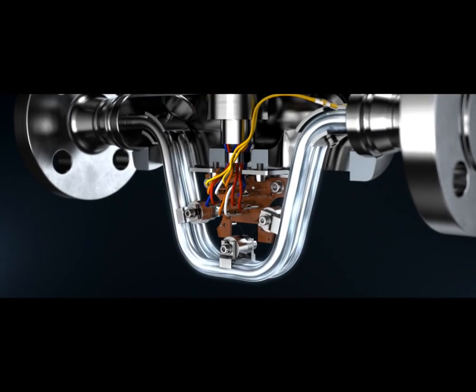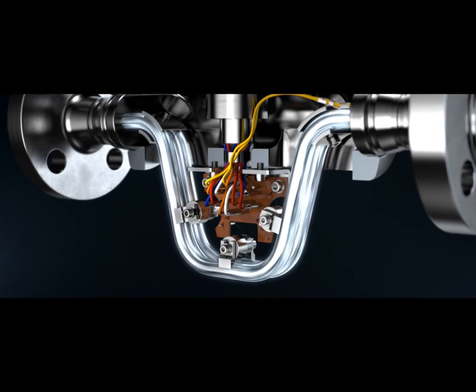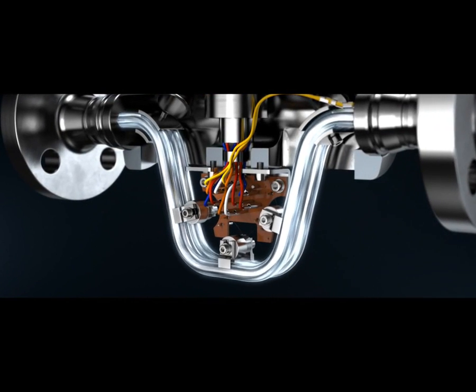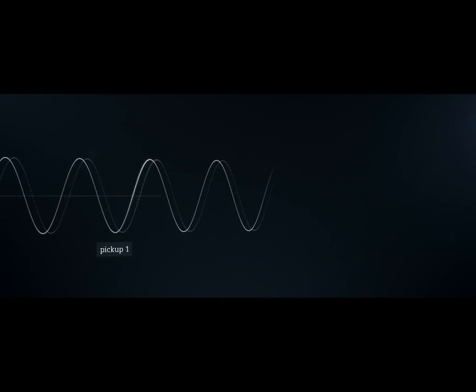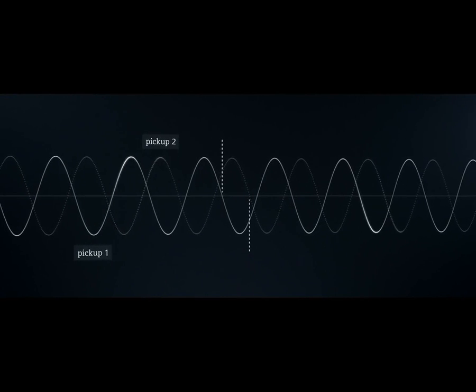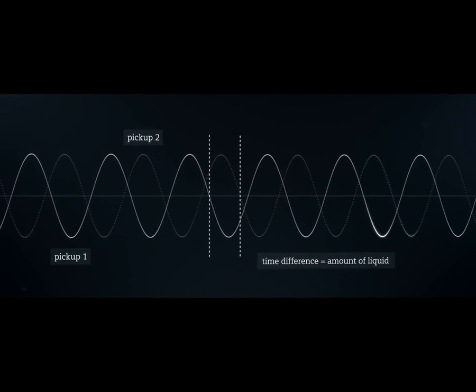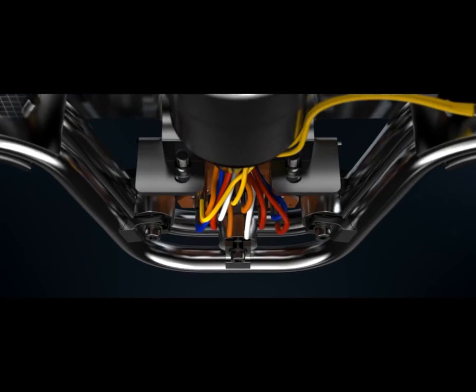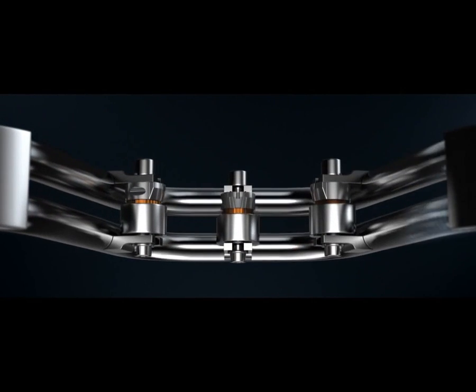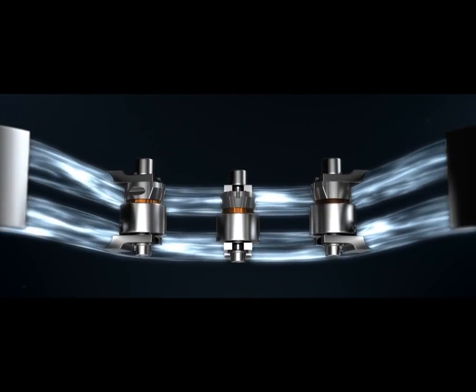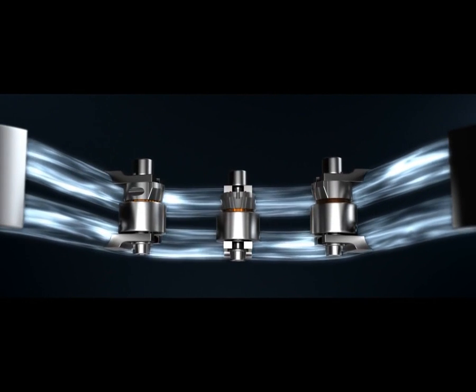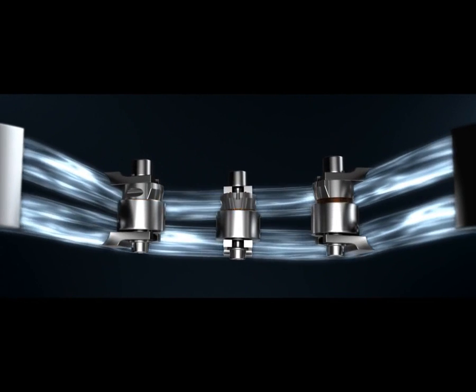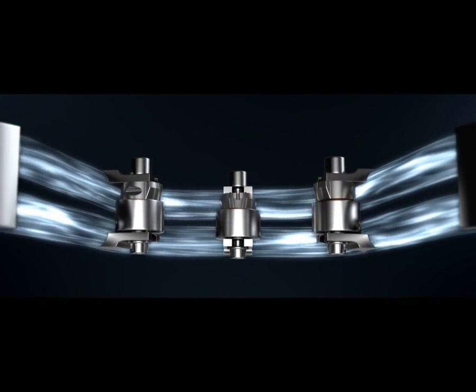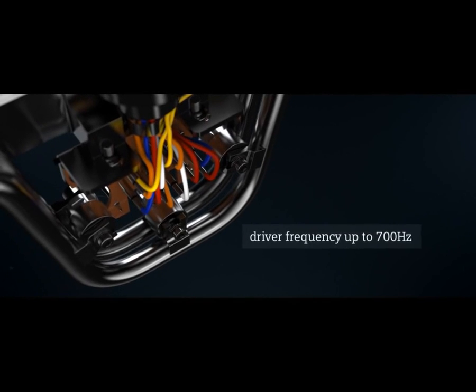If liquids or gases now flow through the tubes, a phase shift occurs, as with a water hose. The pickups measure the spatial and temporal displacement. This determines the amount of liquid or gas flowing through the tubes. The greater the amount, the stronger the tubes oscillate outwards. Siemens presents yet another Coriolis device for measuring mass flow.